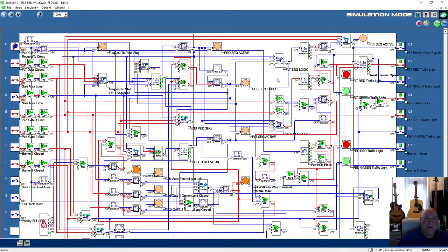Off the back, it sounds like you just changed the wiring, but you'd have to contemplate the stuff in there for tracking the person, for extra safe for the person. You'd still want that. So, yeah, that can stay, I suppose, that logic. Now, the problem is if we just swap the wiring, we're going to swap the extra safe pedestrian crossing over to the forklift truck traversing through. We're not interested in the forklift truck being extra safe. It's the person's safety we're interested in.